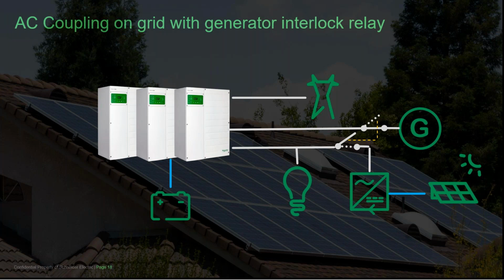Here's an AC coupled system that is grid connected with a backup generator. The interlocked relay prevents the generator from being backfed with excess PV power. Some advantages of AC coupling are better efficiency when PV is supplying the loads in real time, and it's easier to retrofit existing PV systems.